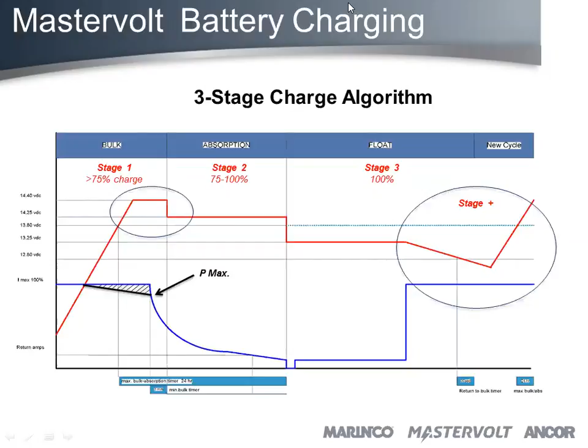Now, temperature compensation. This is always a great discussion. Every charger that we sell will have a temperature sensor. And the reason that we do that is, look at this graph, for instance. First of all, I don't know if you guys noticed, but this is a fact. Every 5 degrees C over 25 degrees C will cut your lifespan on your battery in half. So if your battery sits full time at 30 degrees, and it would normally last 5 to 6 years, you're lucky if you get 3 years out of it.